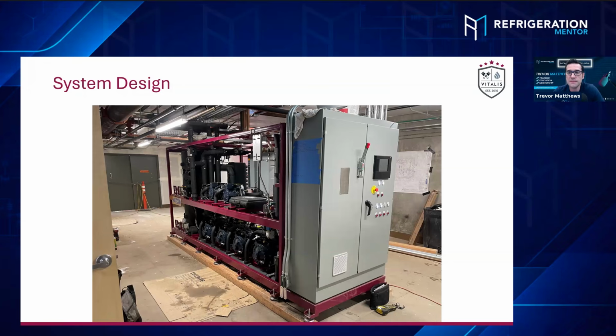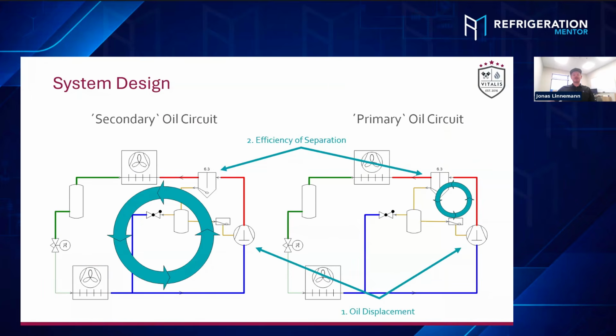So there's a few different ones. For these typical booster systems, we go back to this picture. It's very normal to have an oil separator, then draining the oil back into the oil reservoir, which is stored under lower pressure, and then you feed that back to the compressor. That's the most common way of oil systems.